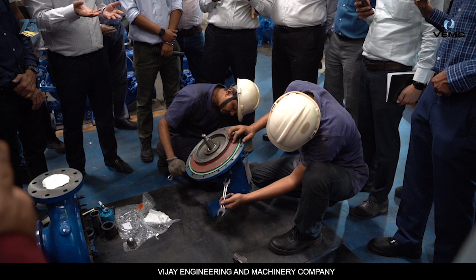Even if there's a seal issue, if the rotating part becomes jammed, there's a higher possibility the pump won't run properly, the motor will draw higher current and trip the panel since we've set that range. These are two reasons that can hinder firefighting. Fire won't happen on our schedule, it happens when it has to, and we don't want the pump to fail then.